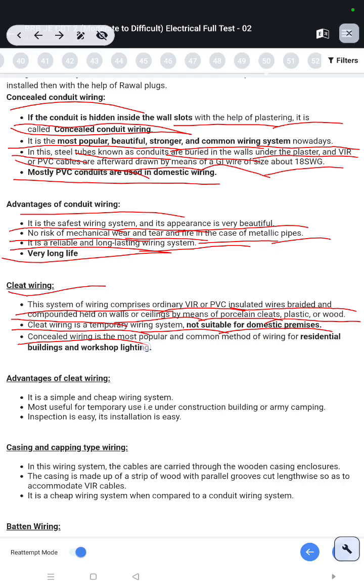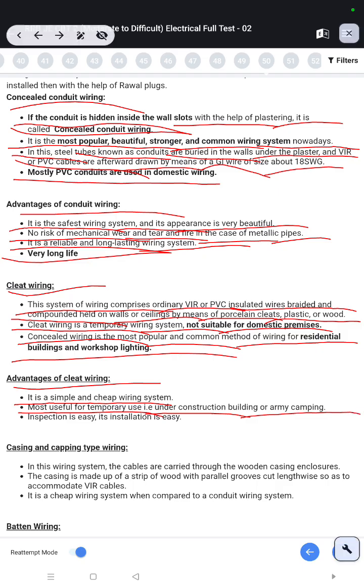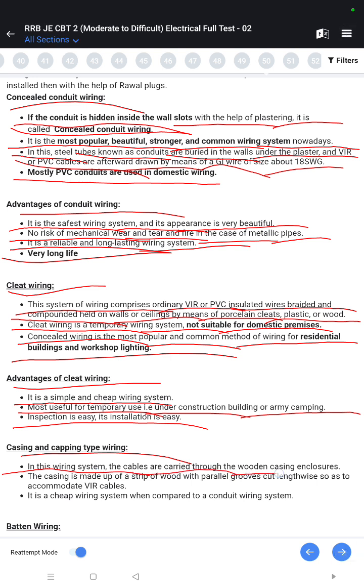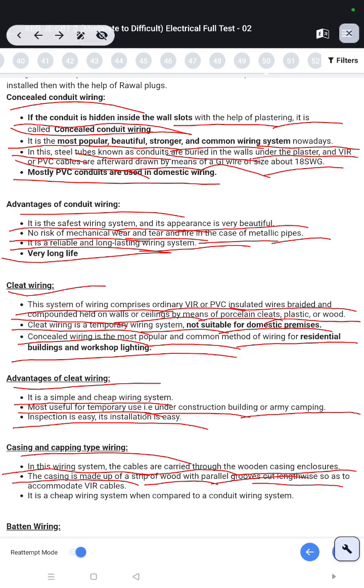Concealed wiring is the most popular and common method of wiring for residential building and workshop lighting. Advantage of cleat wiring: it is a simple and cheap wiring system, most useful for temporary use under construction buildings or army camping. Inspection is easy, its installation is easy. Casing and capping type wiring. In this wiring system, the cables are carried through the wooden casing enclosure. The casing is made up of a strip of wood with parallel grooves cut lengthwise so as to accommodate VIR cables. It is a cheap wiring system when compared to a conduit wiring system.